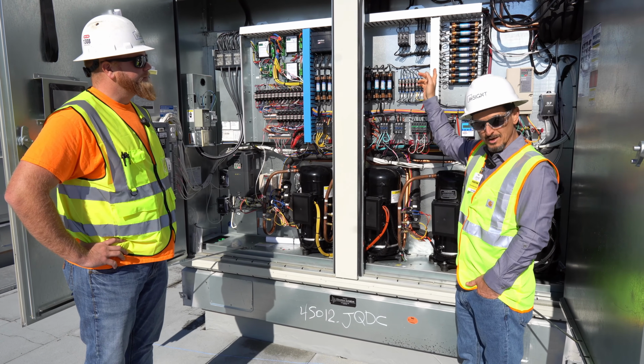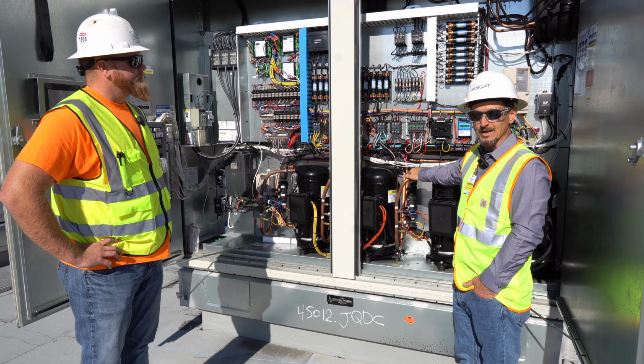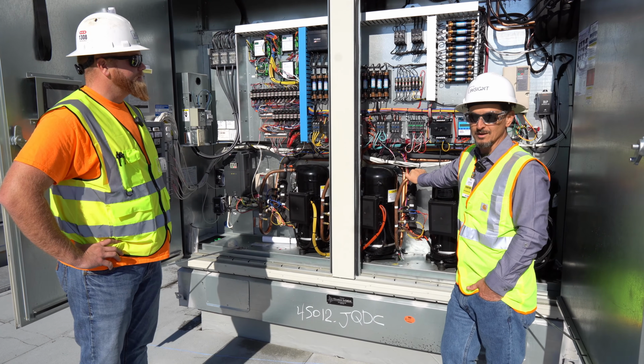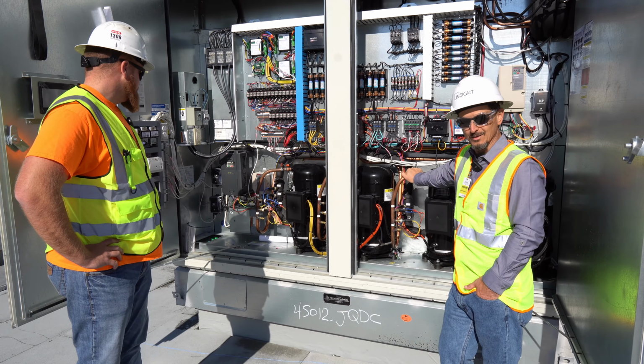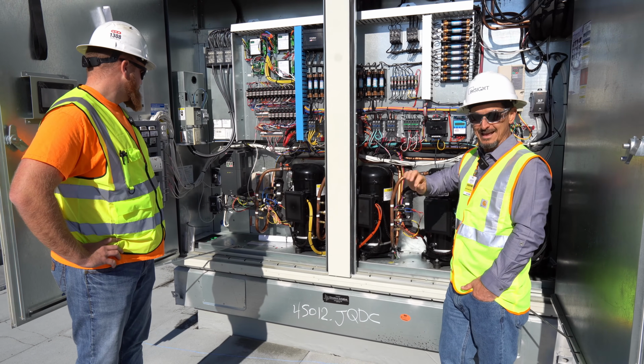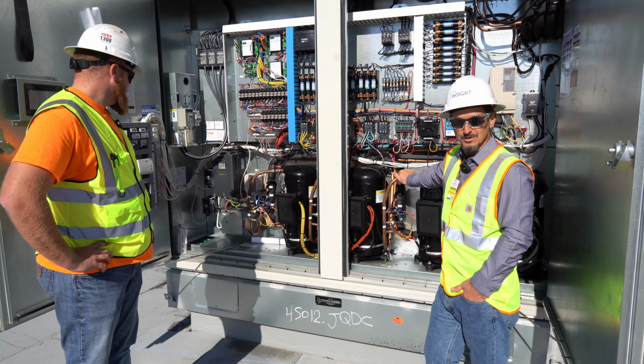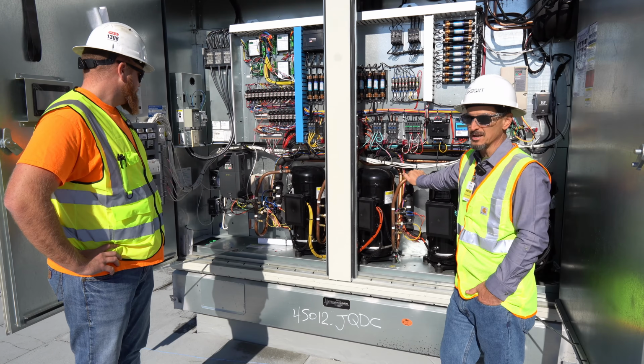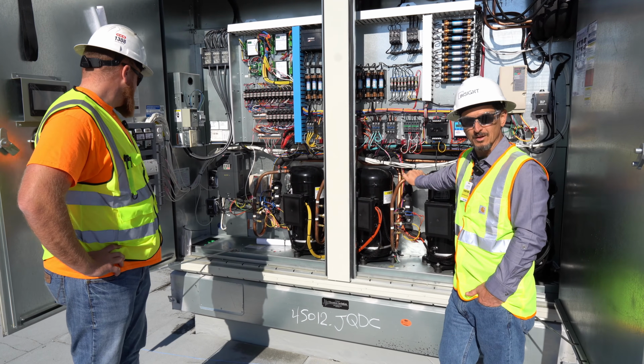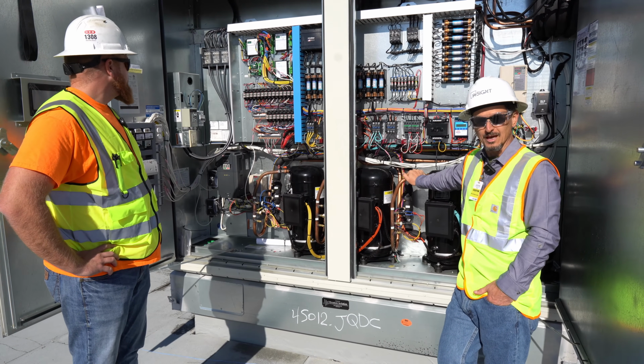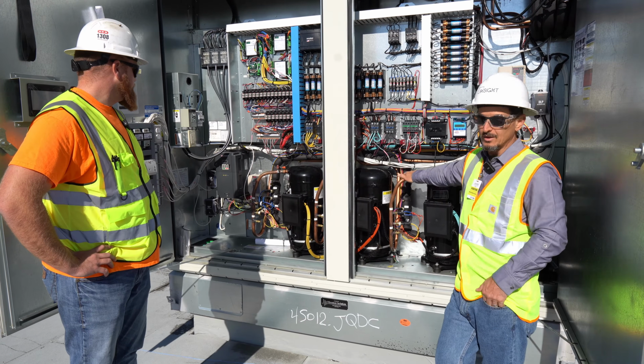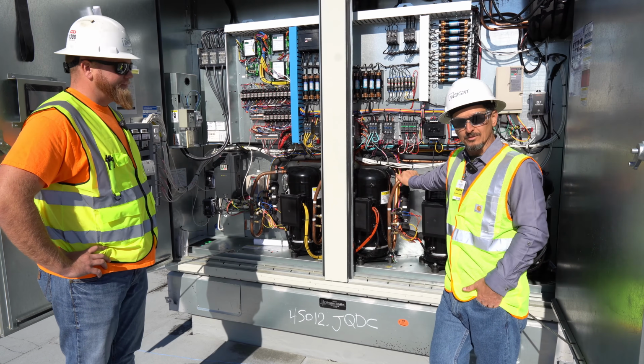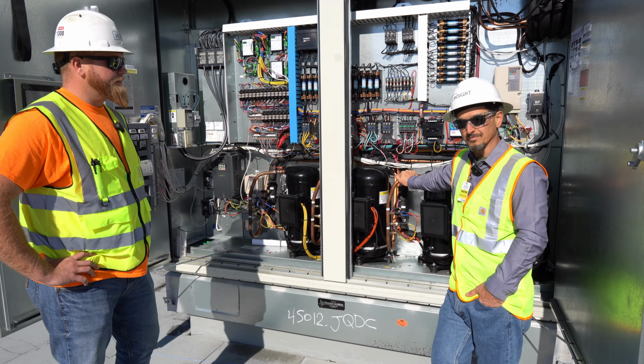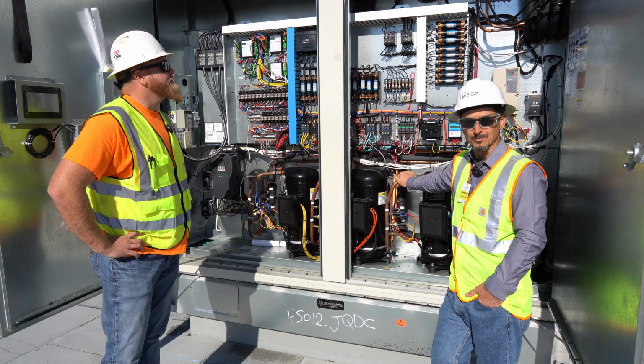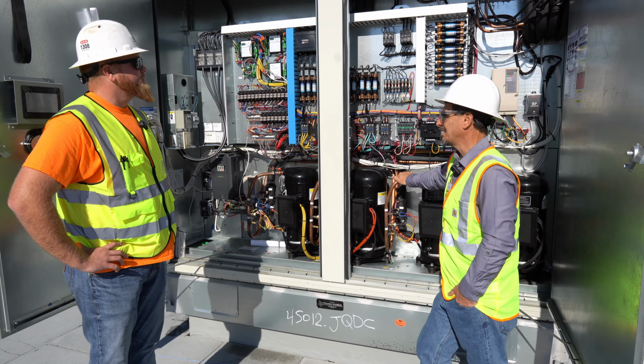The 3-way modulating hot gas reheat valve diverts the gas to the hot gas reheat coil that we looked at before when we need the reheat. So it's really nice because you can modulate that and really nail the leaving air temperature, as opposed to on-off reheat, which we don't see that very much anymore. That used to be kind of a standard, and modulating was this really super premium deal, but it's pretty common for most highly configurable unit manufacturers. So anyway, back to the controls.